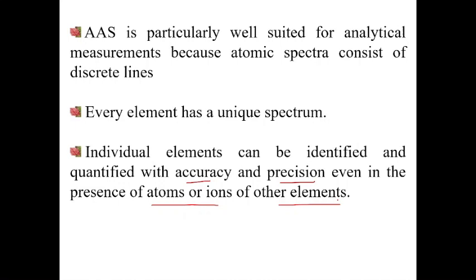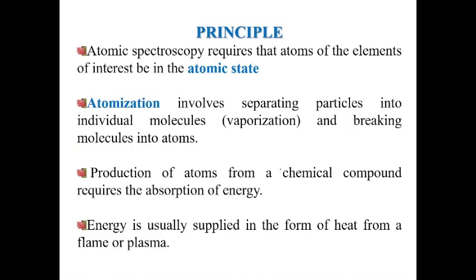The atoms of the element of interest must be in the atomic gaseous vapor state — this is the first criterion. Atomization involves particles being converted to molecules, then molecules being converted to atoms using suitable energy. Production of atoms from chemical compounds requires supply of energy, usually in the form of heat — either using a flame or a plasma. Plasma is the fourth state of matter, consisting of ionized gases and free electrons, with temperatures exceeding 10,000°C.